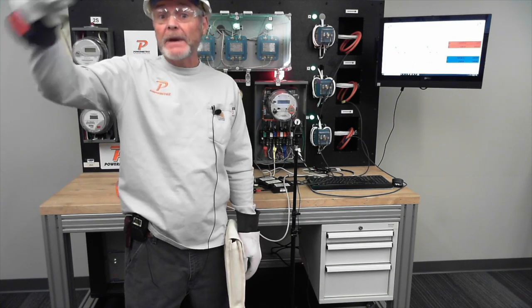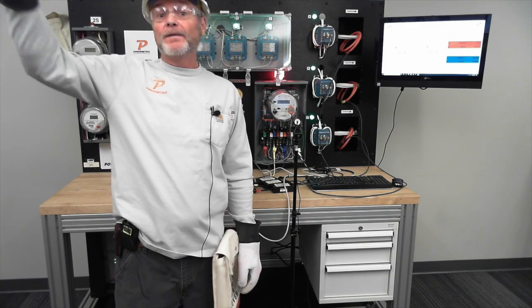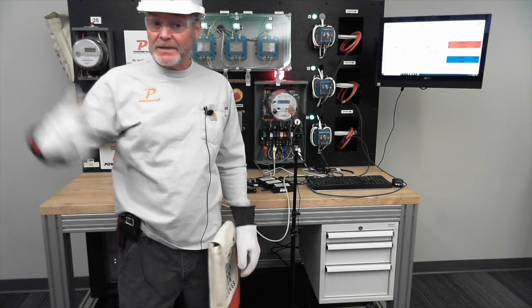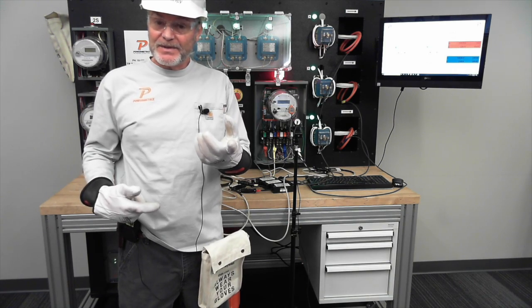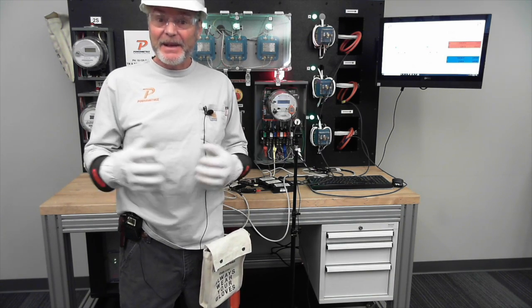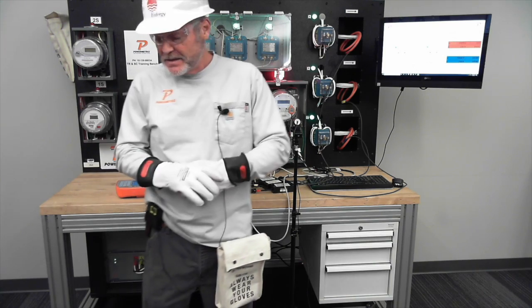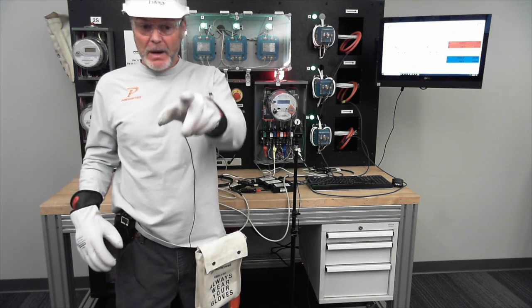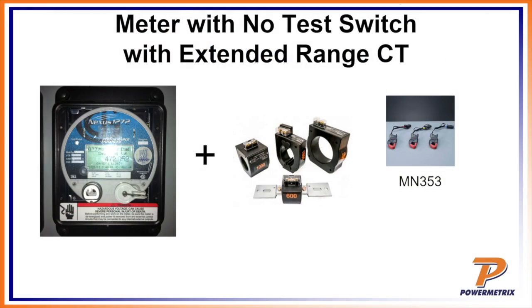Right? So when I have 3, now I'm up to 15. When I go to a rating factor of 4, I'm up to 20 amps. Remember we showed the ratings on those probes earlier. They were 10 amps. So what you have to do then is bump up and go to the 353s, which are rated 200 amps, if you're going to use them on extended range CTs. So if they have rating factors of 3 or 4, the 10 amp probe is not going to work anymore.